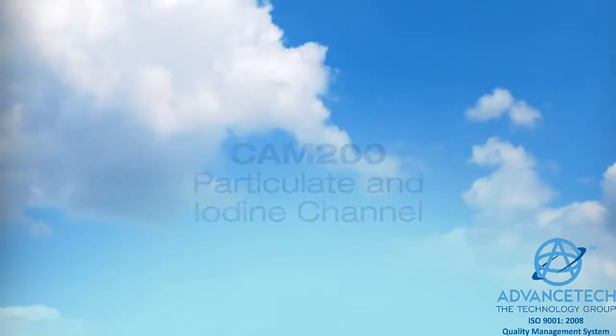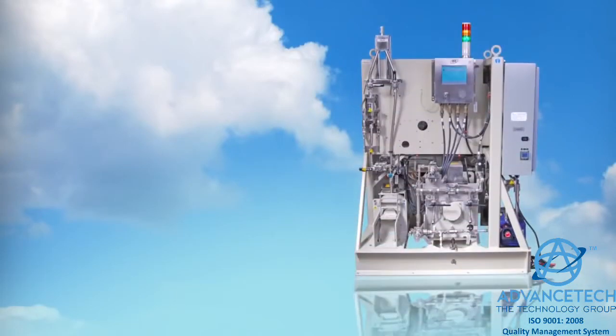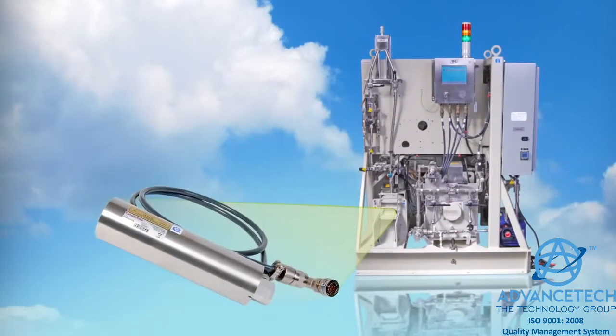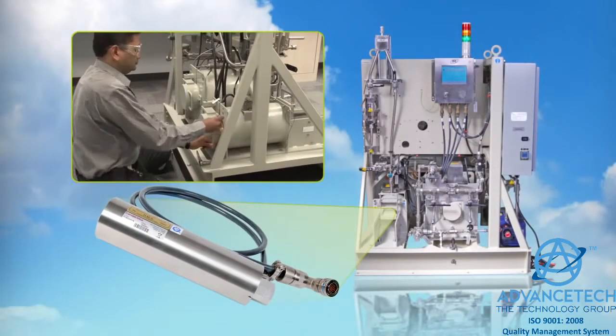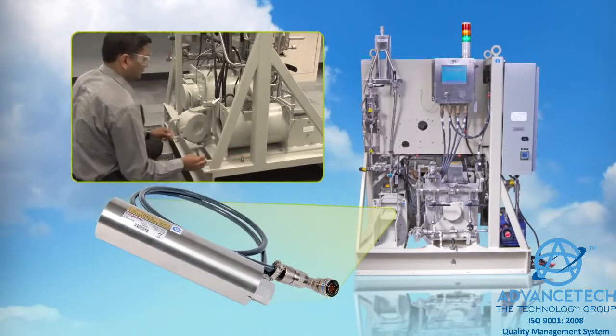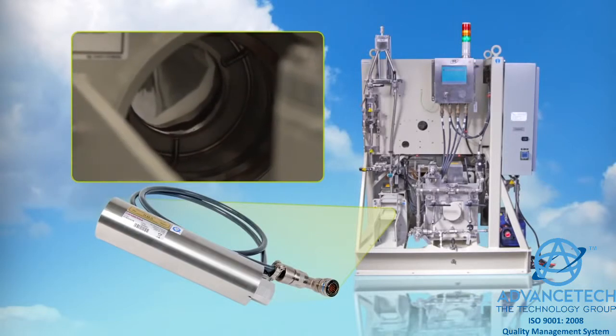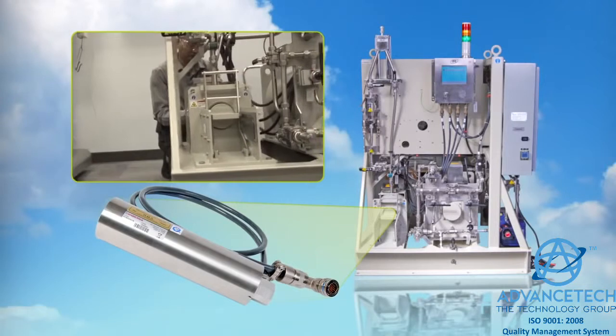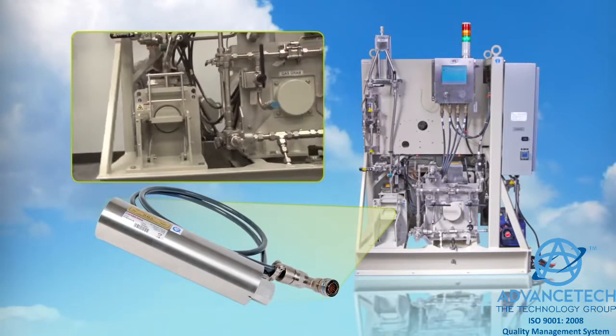For this application, we are employing a uniquely designed detector which allows us to offer a combined particulate and iodine channel. It uses a plastic scintillator for beta particulate and a BGO crystal for the gamma iodine measurement or detection.